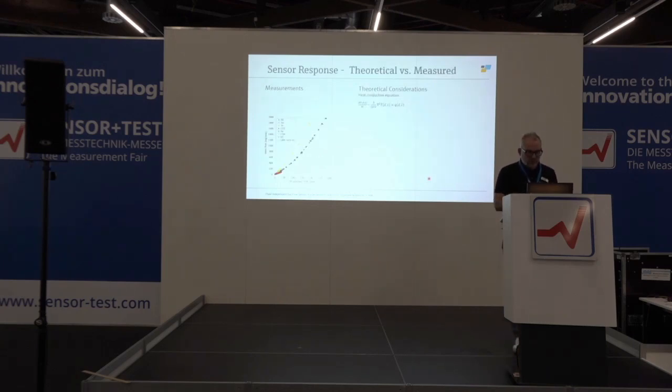So let's see how it works in practice. So we have a calibration with, now we have a 0 point corrected raw value of the sensor plotted against mass flow, because it's basically mass flow which is the main importance of the output, delta T output.